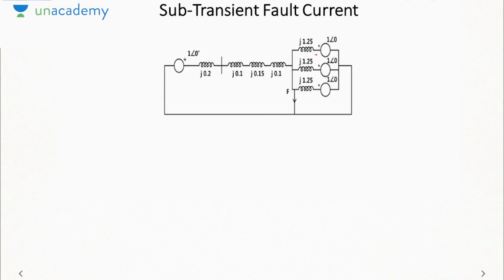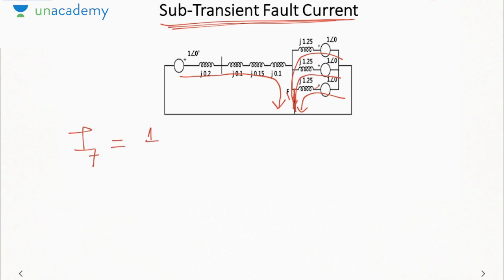Now the first question that we have to solve is to find the subtransient fault current. That is the current going into the fault during the subtransient period. Since we are talking about subtransient, I have used the subtransient reactance of the motor. Since the fault is occurring at F, we have grounded the point F. Now see how the current will flow. Current will go like this from the generator, from this motor like this, like this, and like this. All the machines will be delivering current into the fault, and as I told you, under faulty condition the motor will act as a generator and deliver current to the fault. Now the fault current will have four components. First, coming from the generator, 1 divided by how much is the reactance: 0.1, 0.2, 0.3, 0.45, 0.55.